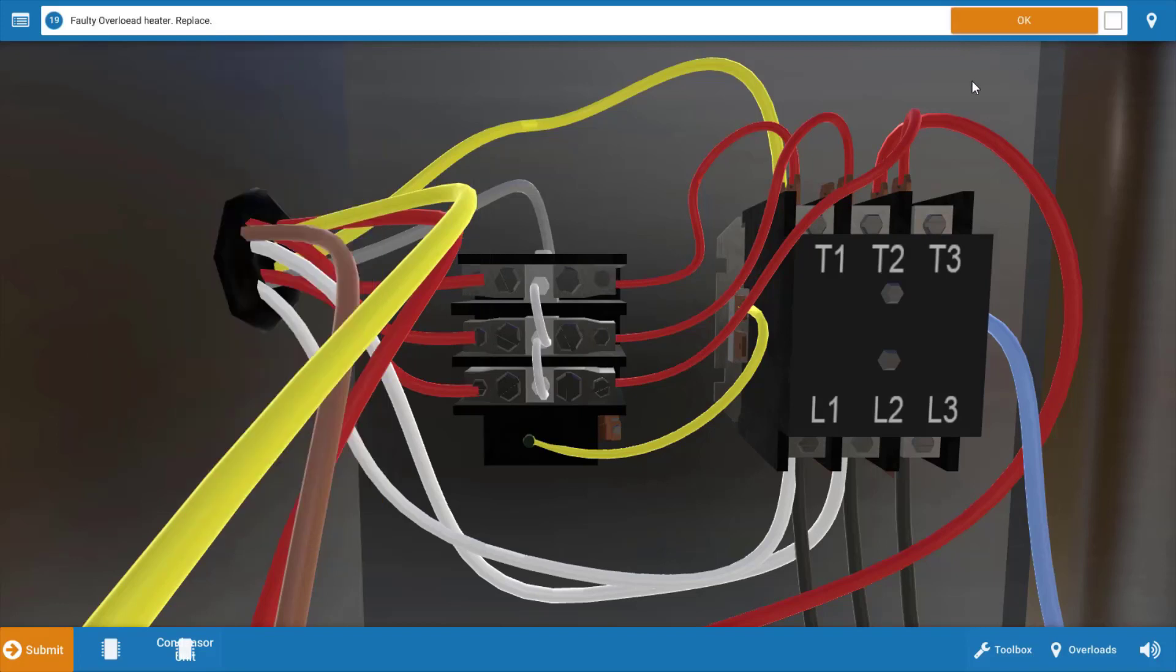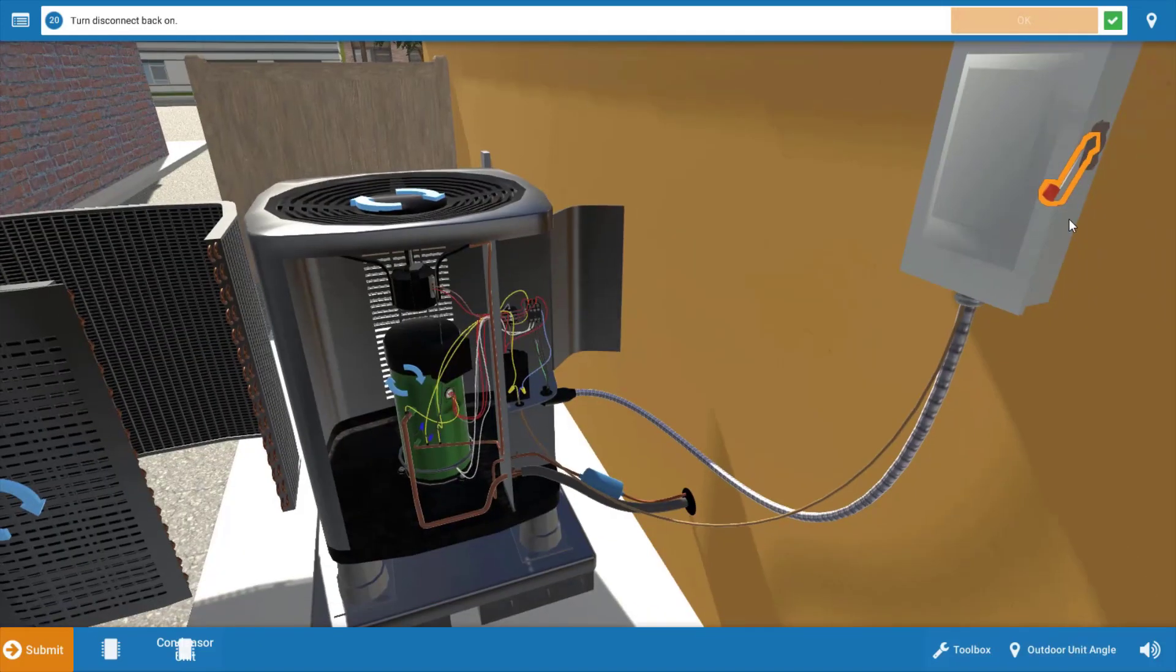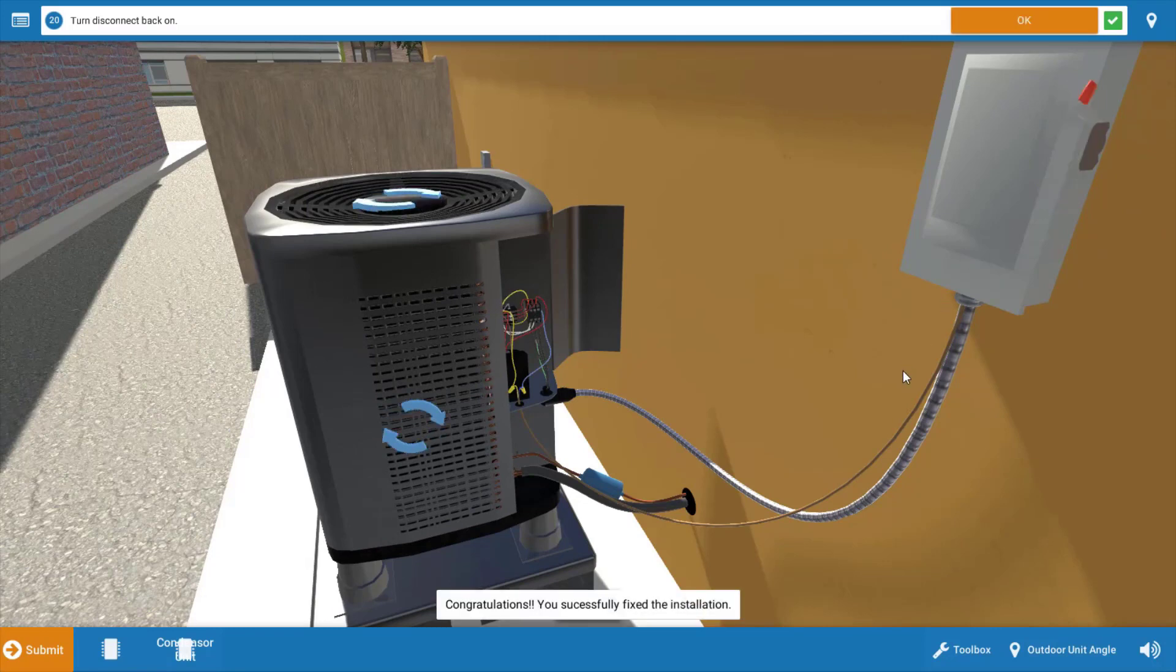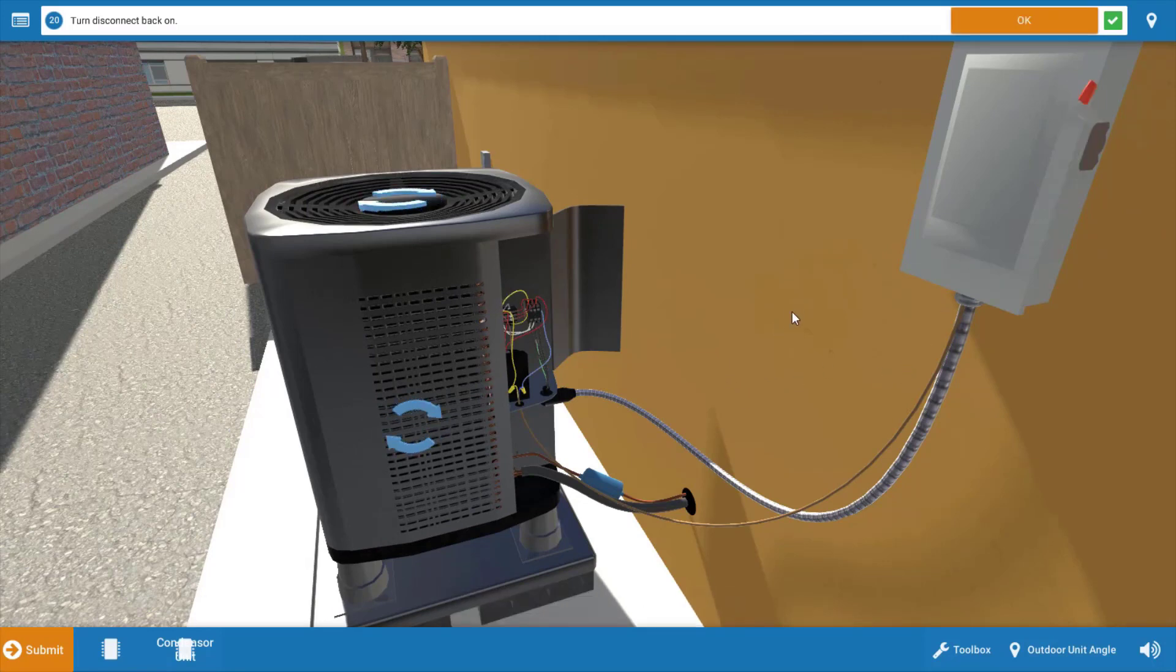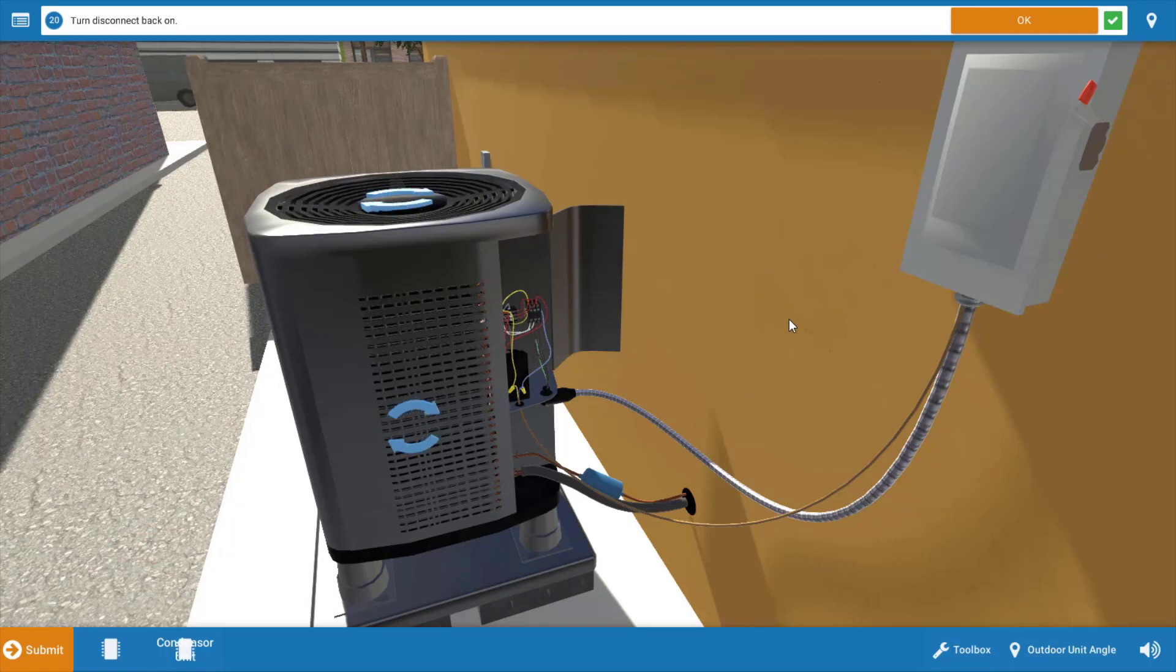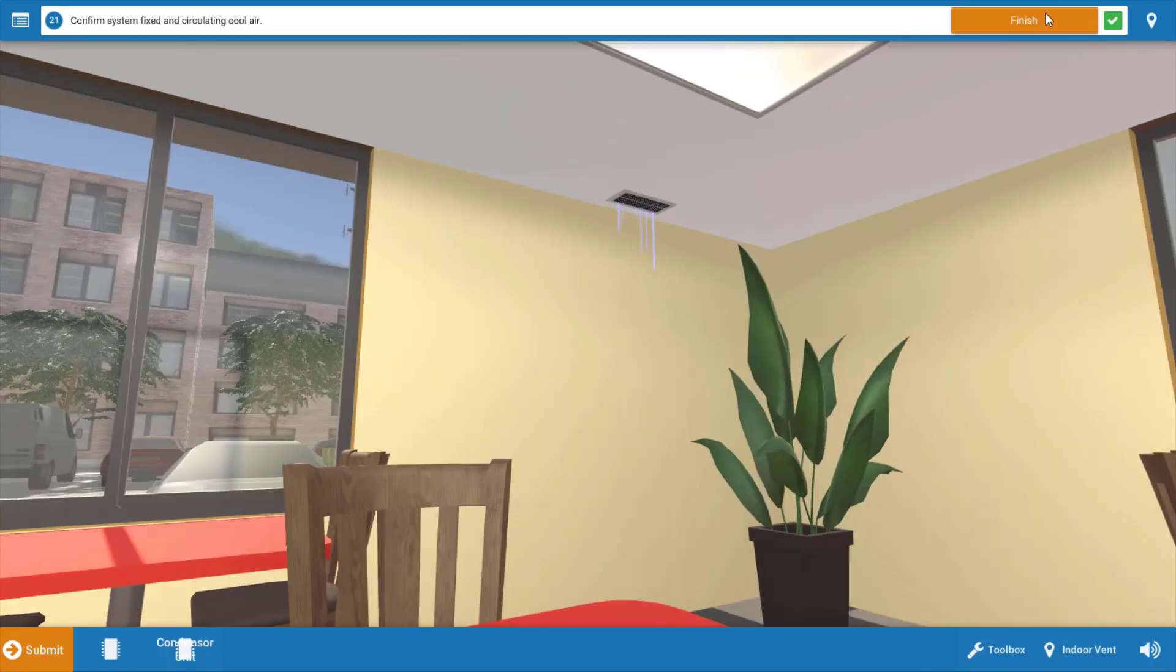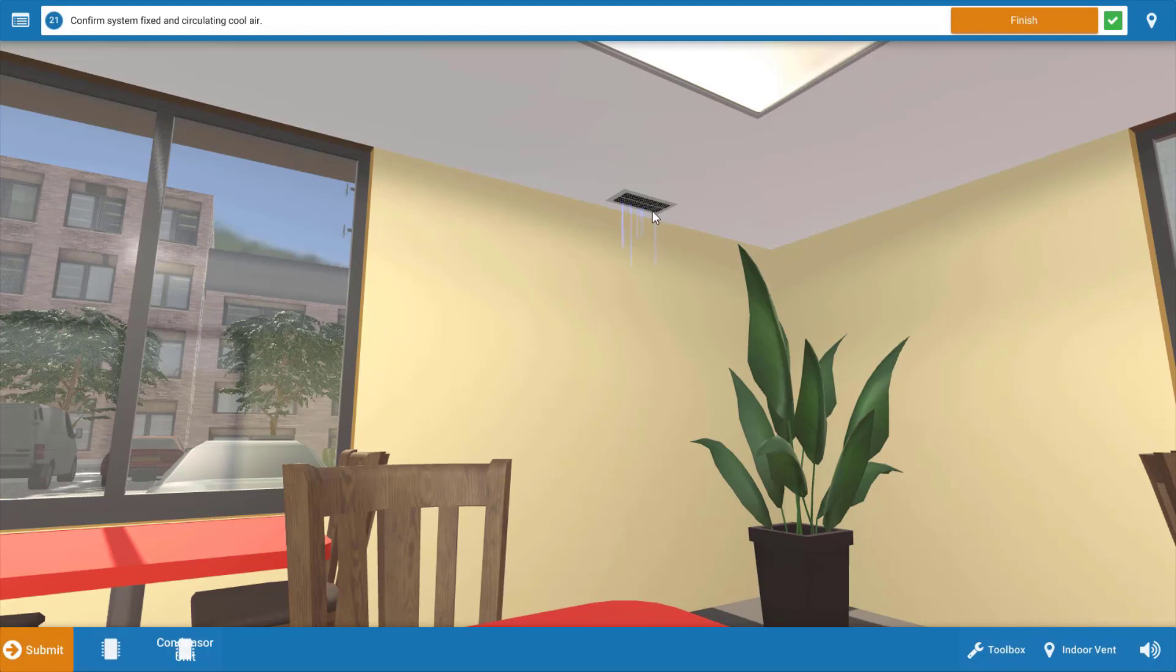Our next step is to turn the power back on and close up the unit. When we do this we're going to want to watch one full cycle of operation to make sure all loads are operating properly, and maybe replace the filter if necessary for a little added value. Click okay, and last but not least we want to go to the space to verify that cool air is being delivered. We can see from the graphic in this ceiling register that we are in fact delivering cool air to the space.